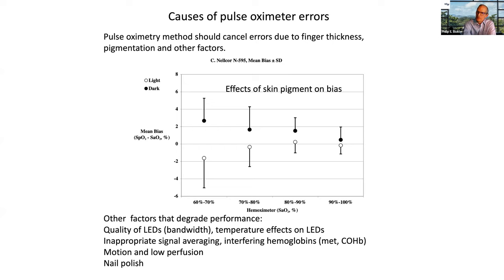A lot of people were surprised by this. They said, oh, dark skin looks like deoxygenated blood, so why wouldn't a pulse oximeter read too low in someone who has a lot of melanin in their skin? Well, just the opposite is true, actually. It's a property of the optics and the way in which the saturation is determined that melanin actually produces a bias in the positive direction. So pulse oximeters at the time of this study in 2005 tended to read too high in subjects with dark skin pigmentation.